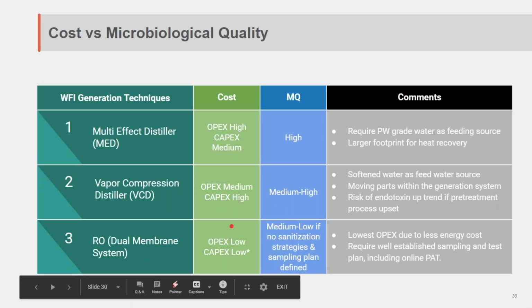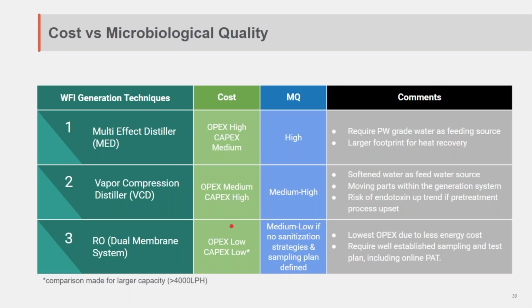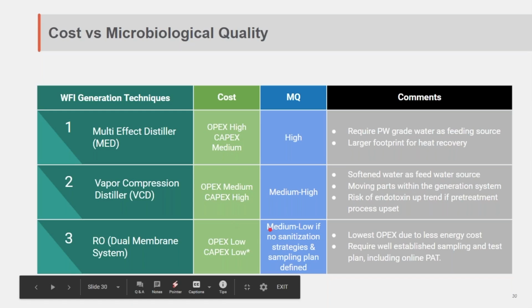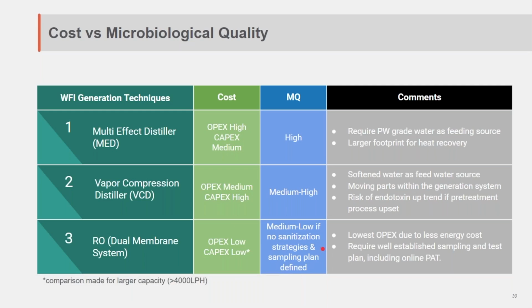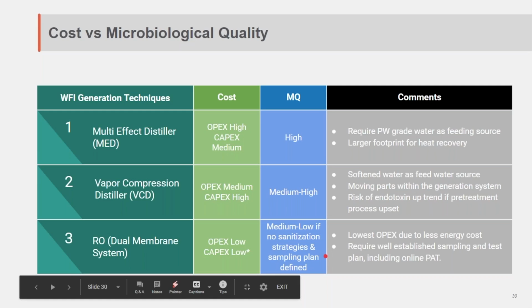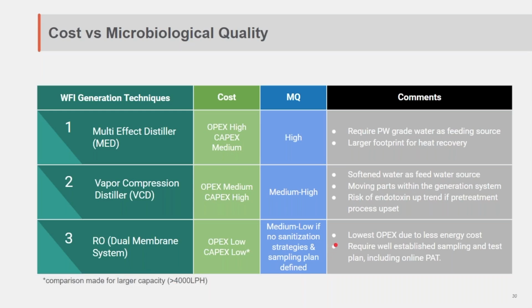And as I explained in the schematics previously, for instance, on the Orion unit, we have the UF there for this specific purpose. Historically, ROs were perceived as a risk because prior to hot water sanitizable membranes, we had to chemically clean them and they were cold systems. And there was a high risk of biofilm buildup on the RO membranes. But with regular hot water sanitization, we know that's not the case anymore, and the microbial growth is well managed. So we're using heat to remove that risk.